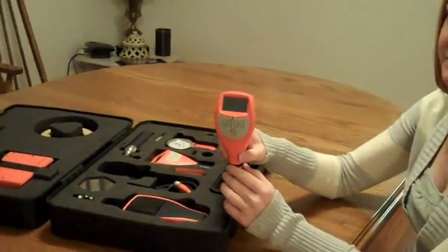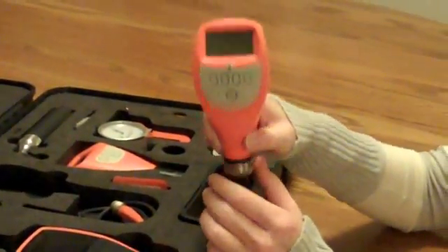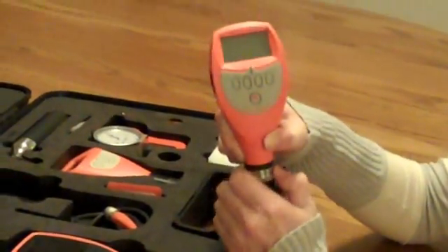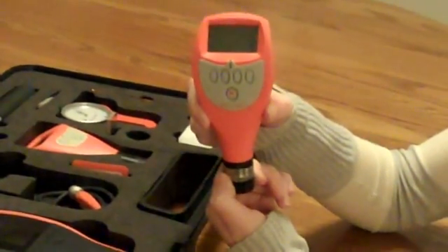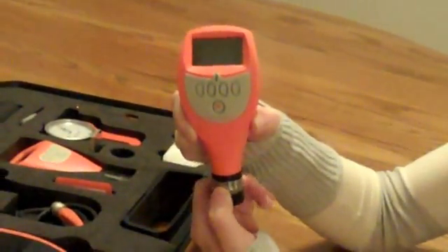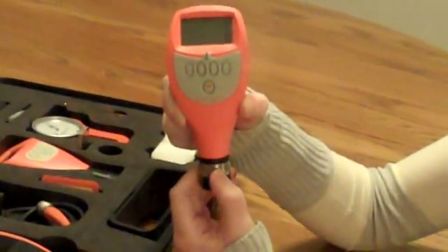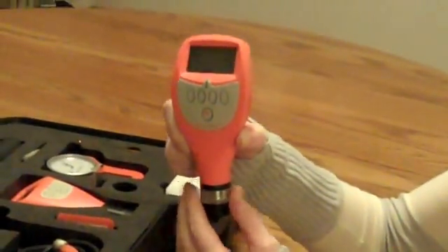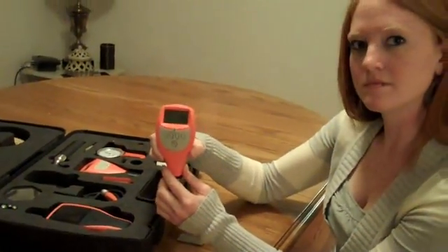That's right. The 456 comes in a variety of options for probes. You can either have the probe integrated into the gauge, or in this case, this is a separate gauge with a probe that is a plug-in integral probe. You can have all different types of probes, but this one is meant for single-handed use and just screws in and out. All of the different probe options are calibrated in the same way, and that's what Kelly's going to show you today.